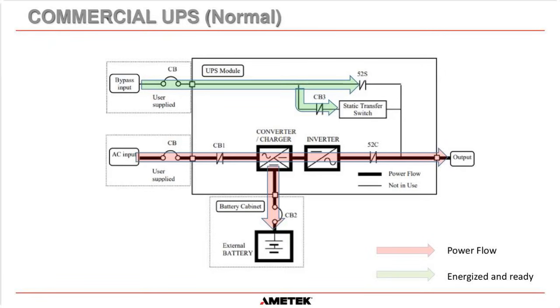So here is the standard operation of a commercial UPS. Okay, in normal operation, the red is the power flow. You can see it, here's the key, and the green is energized and ready. So in normal operation, power flows from the AC input into the charger converter. Okay, in a commercial UPS, it takes that 480 volts and just directly, using a diode rectifier bridge, not a controlled bridge, it rectifies that 480 volts into roughly 650 volts DC. Okay, so you're going to have 650 volts feeding the inverter DC, and that DC gets turned into AC, which is at 480 volts, and then it flows out this way to your output circuits.